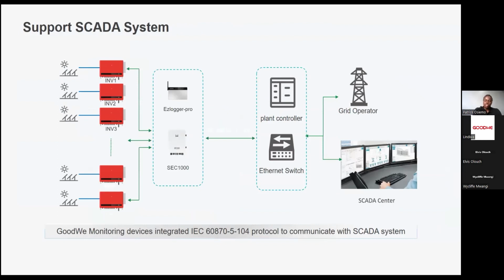In case you want to scale up your system or you want centralized monitoring, GoodWe is compatible with, or can be linked to, a SCADA system. So through the EzLogger, bigger plants, bigger installations, bigger controllers. The SEC 1000 and the EzLogger are capable of communicating through the local network, and this can be interlinked or interconnected to the local SCADA system or the SCADA center. That is if you're using the IEC protocol.